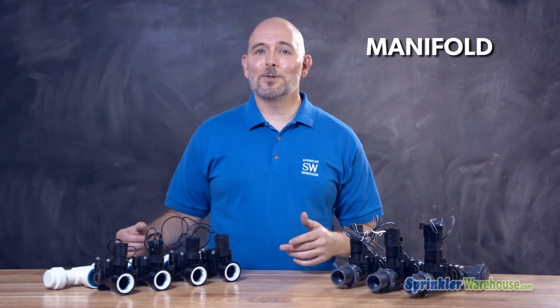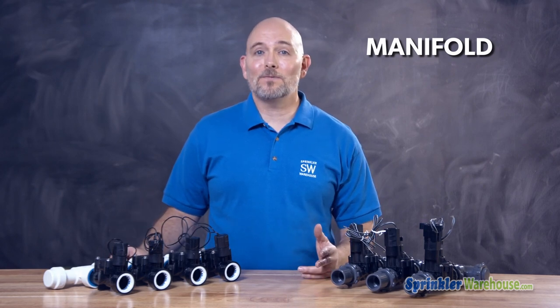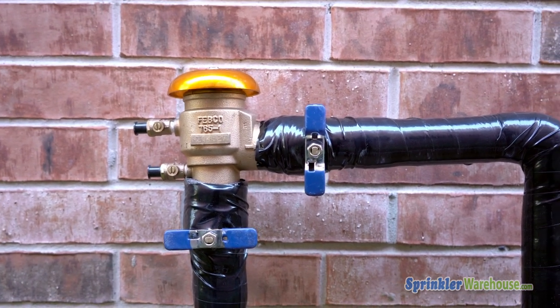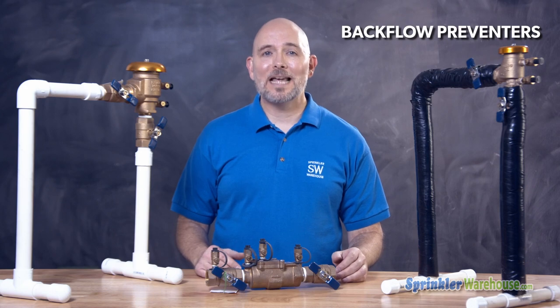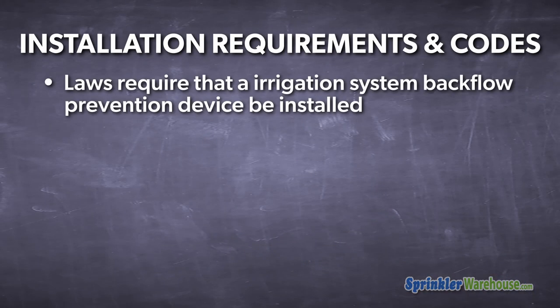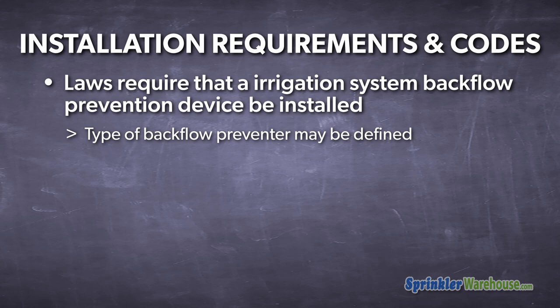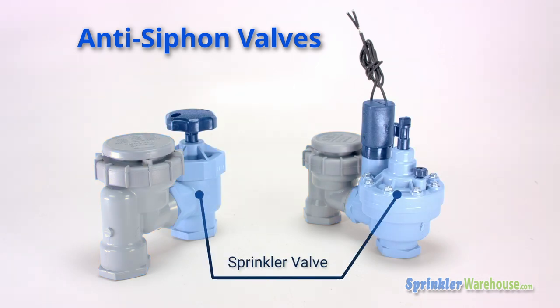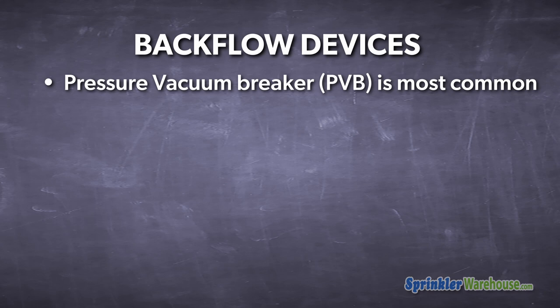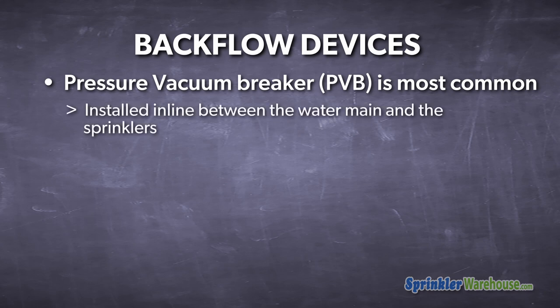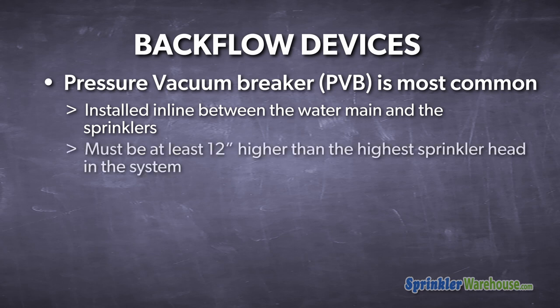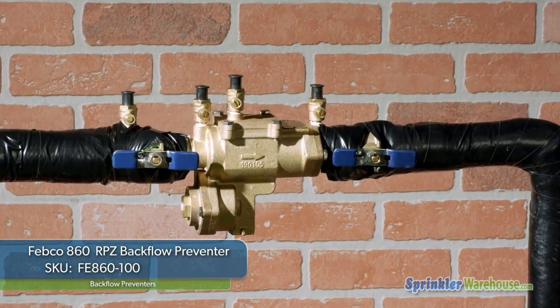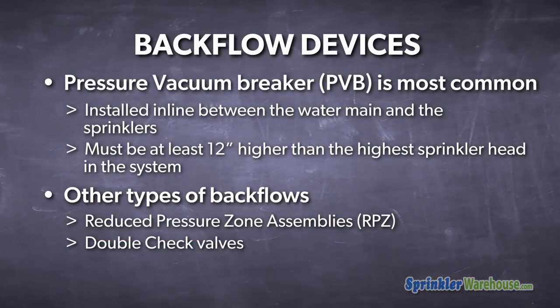Valves are often grouped together in a manifold. By grouping valves, it increases the ease of maintenance and often reduces the cost of piping. Backflow preventers — often just called backflows — are devices used to prevent back siphonage or back pressure from contaminating drinking water. Most water districts require some type of backflow prevention device in an irrigation system. Laws and regulations in your area may require a specific type of backflow and specify where it can be installed. The most common type in residential areas is a pressure vacuum breaker, which must be installed in line between the water main and the irrigation system, at least 12 inches higher than the highest sprinkler head. Other types include reduced pressure zone assemblies and double check valves.